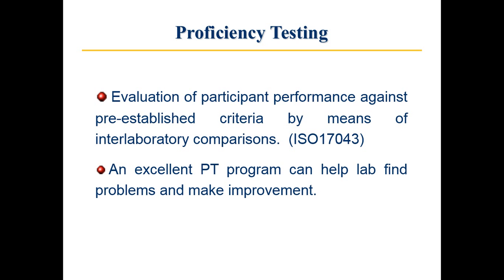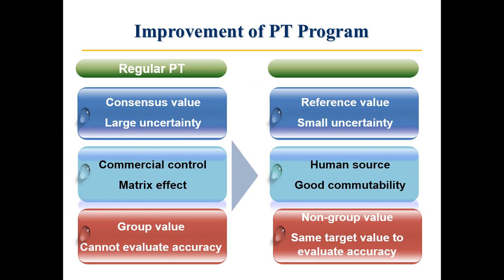Proficiency testing is to evaluate a participant performance against pre-established criteria by means of inter-laboratory comparisons. PT programs is one of the key methods to assure the quality of clinical labs. An excellent PT program can help labs find the problem and make improvement. We usually consider PT program from the following 3 aspects: value assignment, PT materials commutability, and statistical analysis.